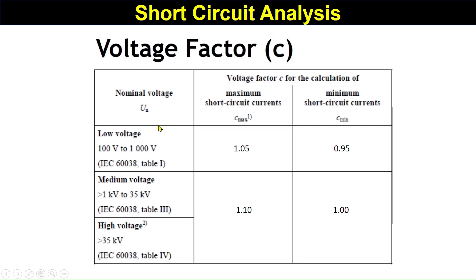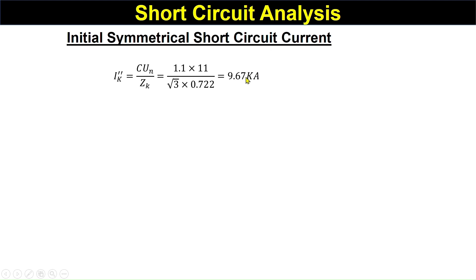The voltage factor c is taken from IEC 60038. For low voltage (100 V to 1 kV), c_max is 1.05. For medium voltage (1 kV to 35 kV), c is 1.1, and for high voltage it is also 1.1. Since 11 kV falls in the medium voltage range, we use c = 1.1. This is taken from IEC 60038, Table III and Table IV. So the calculated initial symmetrical short circuit current is 9.67 kA.